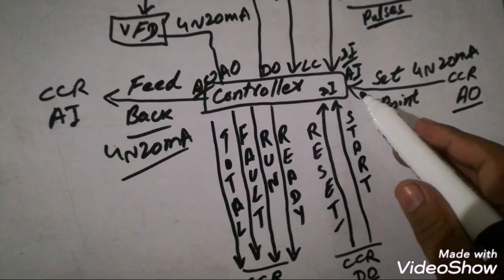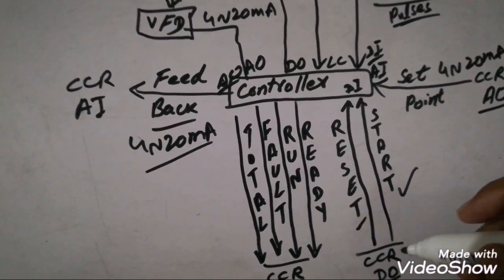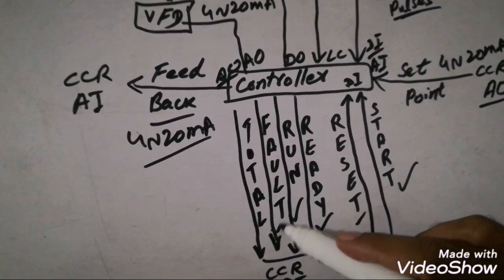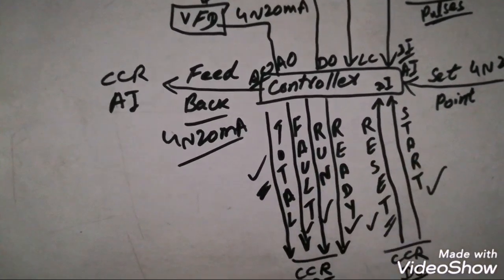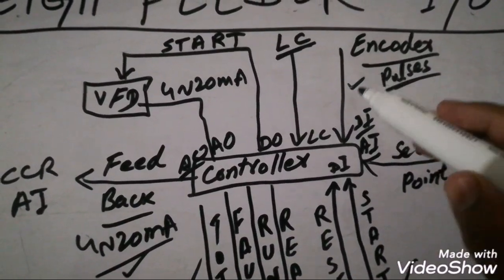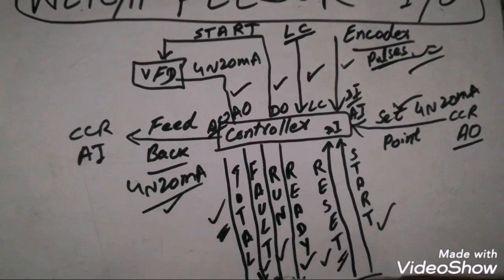These are the main inputs and outputs of the weigh feeder. To summarize: the operator gives a start command; if the weigh feeder is ready it starts running; if there is a fault, after rectification the operator can reset it. For each ton, the controller generates a pulse. The feedback is 4 to 20 mA, along with encoder pulses and load cell signals. The controller also sends a start command and analog set point to the VFD.